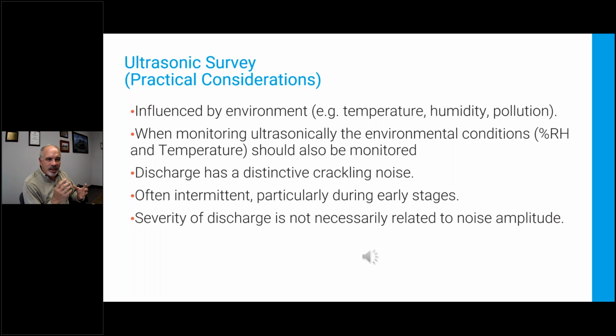When you're doing a survey, you need to think of some things. The level of PD and the transmissivity of the air for ultrasonic energy varies with humidity. So we want to make sure we record humidity, and if you have an instrument that actually records humidity in the same survey while you're taking the data, that's even better. So when you come back a year later and the humidity is dramatically different and the PD is dramatically different, you've got some cause and effect there. Temperature doesn't have much effect on PD, but if you have a crack and that crack expands when things heat up, that's going to give you perhaps more discharge.